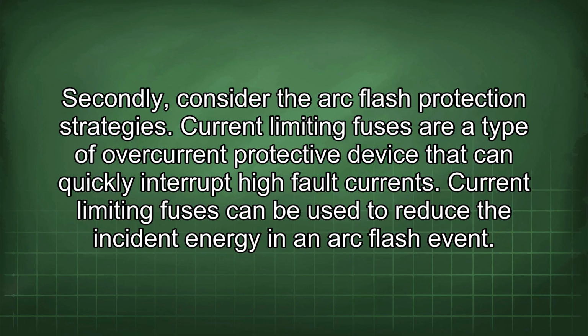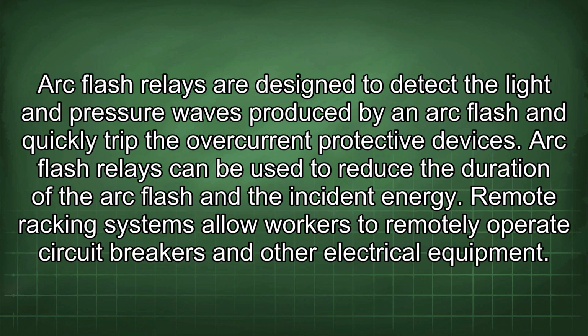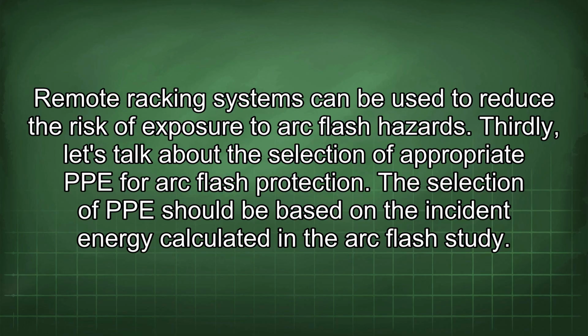Secondly, consider the arc flash protection strategies. Current limiting fuses are a type of overcurrent protective device that can quickly interrupt high fault currents. Current limiting fuses can be used to reduce the incident energy in an arc flash event. Arc flash relays are designed to detect the light and pressure waves produced by an arc flash and quickly trip the overcurrent protective devices. Arc flash relays can be used to reduce the duration of the arc flash and the incident energy. Remote racking systems allow workers to remotely operate circuit breakers and other electrical equipment. Remote racking systems can be used to reduce the risk of exposure to arc flash hazards.